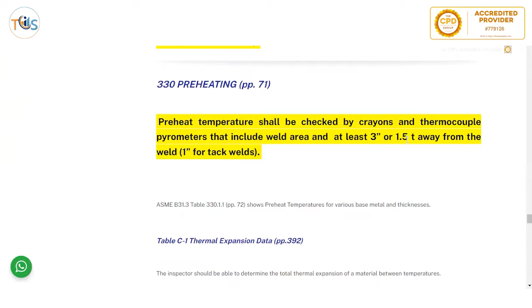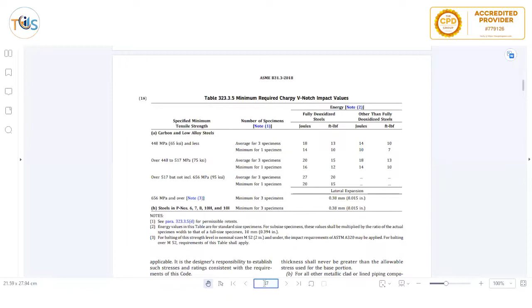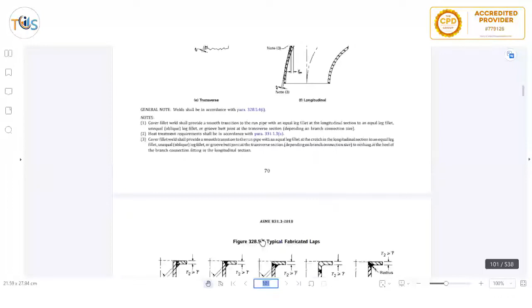So the preheat should be maintained at least 3 inch or 1.5 T, or thickness of the base metal, away from the weld. And also, if you go to page 72, it says what the preheat temperature is. So Table 330.1.1, page 72. Let's go to 72. So if you go here, you can see the preheat temperature.